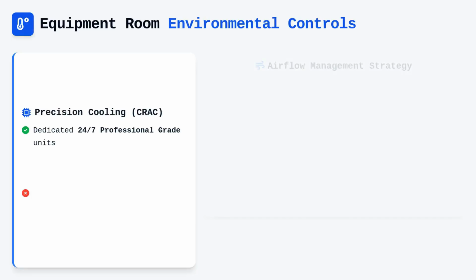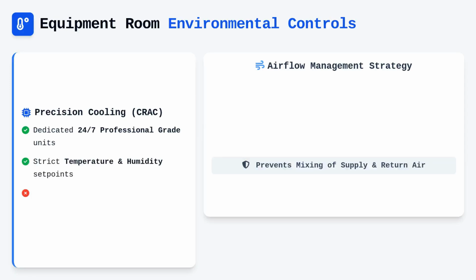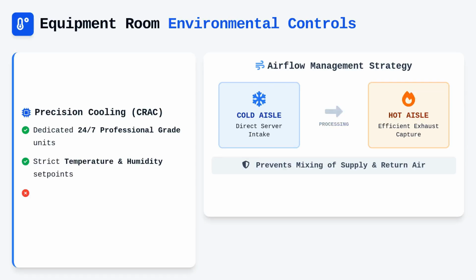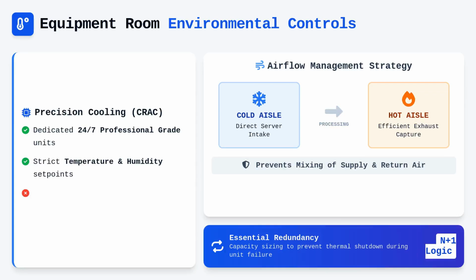We effectively manage this heat by implementing cold aisle and hot aisle containment strategies, which prevent the mixing of supply and return air. This separation ensures that cold air reaches the intake of the servers directly, while exhaust air is efficiently captured and returned to the cooling units. Because these systems run continuously, redundancy is essential. We typically size them such that if one unit fails, the remaining capacity can sustain the heat load without causing a thermal shutdown. Relying on shared building HVAC systems is rarely acceptable if performance targets for the equipment need to be met consistently.